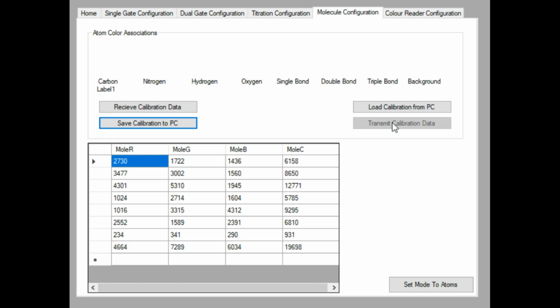So what we heard there was the control unit receiving the calibration data, and so it's now received that previously stored calibration data from the unit. We can set it into the molecular mode or atom mode as it's called here, and then go and use the unit.